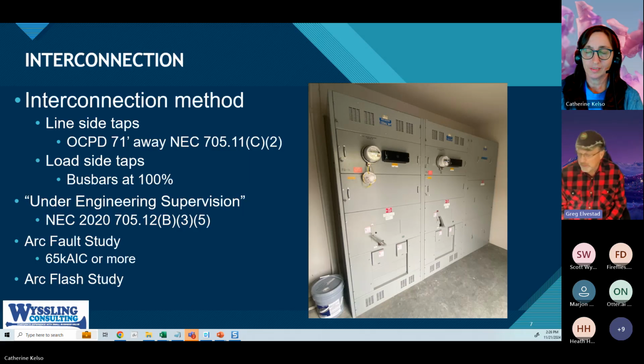Some adjustments in the electrical code give us options but also add restrictions—for example, line side taps. Traditionally you've had to install your overcurrent device within 10 feet of the point of interconnection. Now you've been allowed some leeway to move up to 71 feet from the point of interconnection, using current limiters. Basically, that's a fancy word for a fuse, constricting the amount of current in a fault condition so it keeps from having a thermal runaway situation or exploding and causing a severe fire safety incident at a different location.